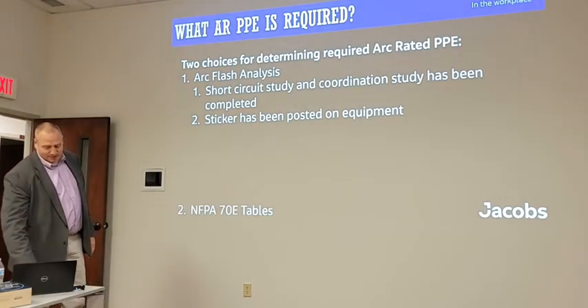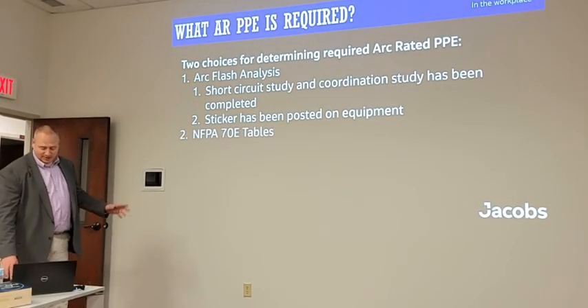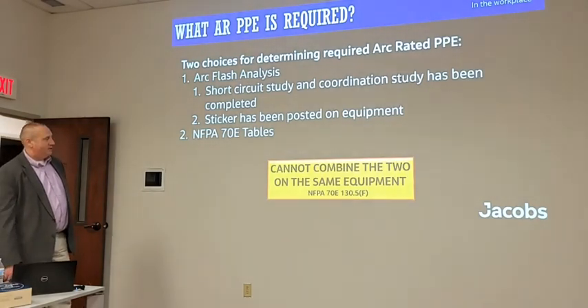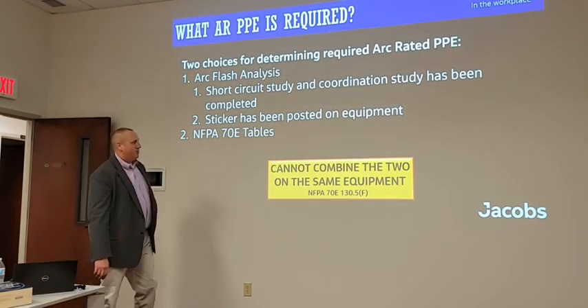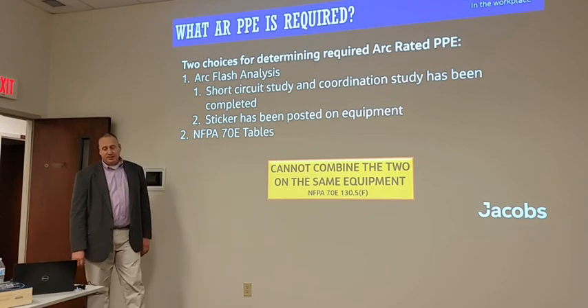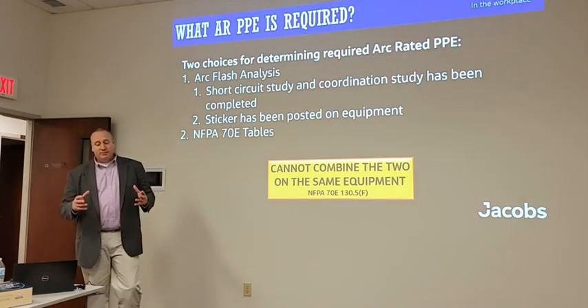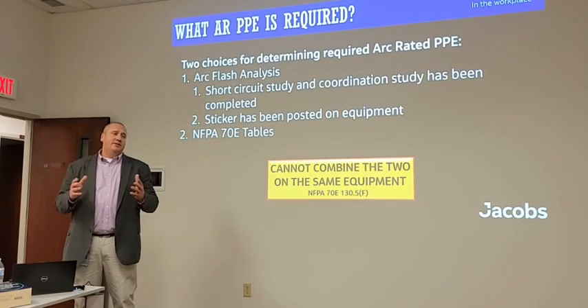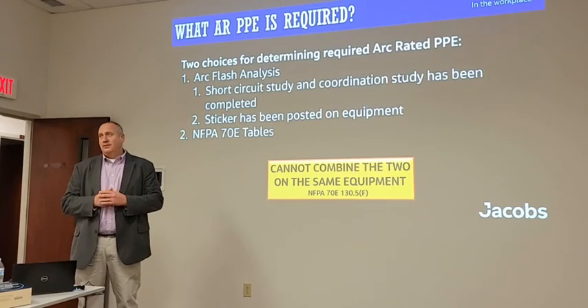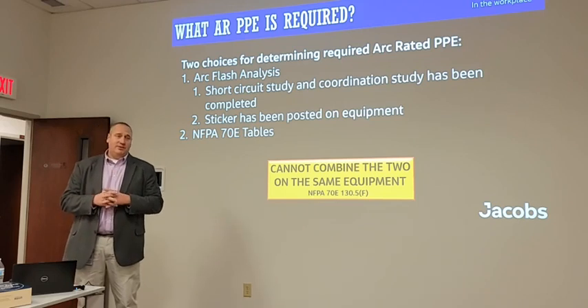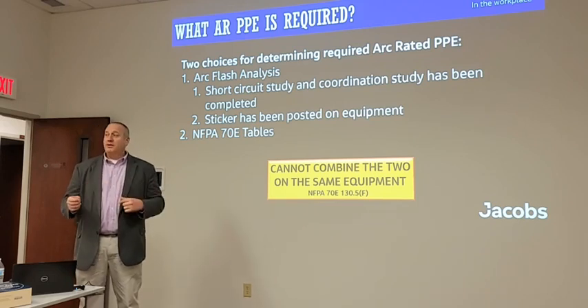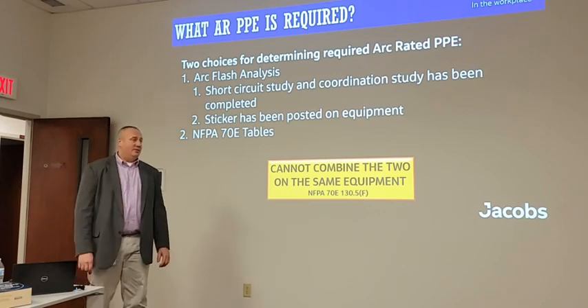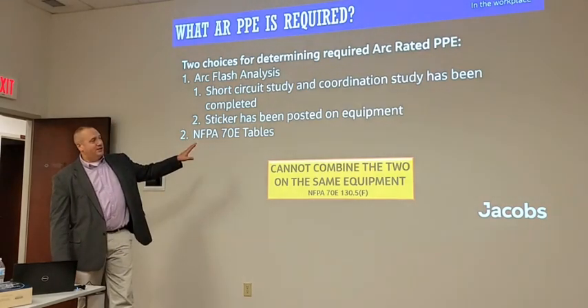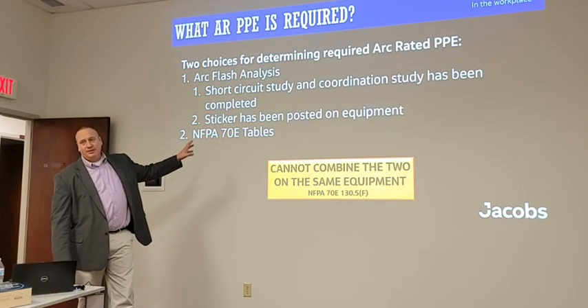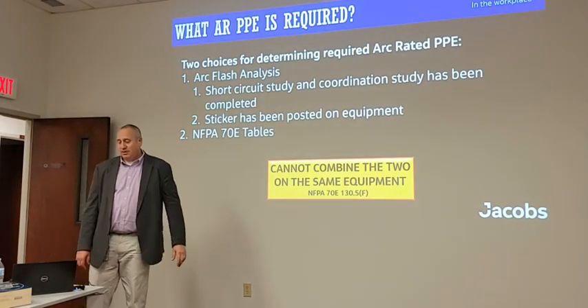I am confident in putting my life in the PPE that's been selected by the arc flash analysis method. The other method is to use the NFPA 70E tables, which we just talked about in probably more detail than you wanted to. But you cannot combine the two on the same equipment, because there's oftentimes where, like operating a breaker, the table says under normal operating conditions, operating a breaker is not an arc flash likelihood, so most people interpret that as when I operate a breaker, I don't need arc flash PPE. But then you go do the analysis on your 480 volt equipment and realize, well, that's a 15 calorie energy coming into that. So now we've got to wear either level 3 or level 4 PPE to protect ourselves.